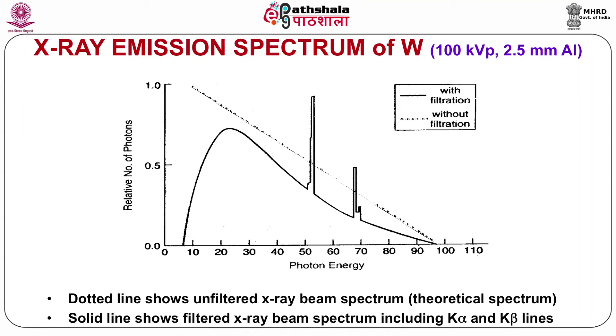The area under the curve, that is the solid line, represents the total number of X-ray photons, both characteristic and Bremsstrahlung. It is observed from this figure that Bremsstrahlung photons are the major component of the X-ray spectrum emitted by the X-ray tubes, and they constitute more than 80% of the X-ray output from an X-ray tube. The contribution of characteristic X-rays to the total X-ray output and the energy range where it occurs in the X-ray spectrum depends upon the target material.